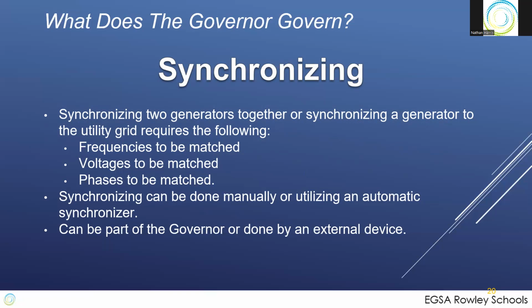When you're looking at, let's say, a generator with a local load and a utility tie point, and now you've isolated from utility, run in island mode for a while, feeding your loads, and now you want to go back on utility, you synchronize back to the utility, and now the genset controller may not be able to see that tie point. You may have another control device at that utility tie point sending a speed trim signal back to the governor on the generator to get it to match utility. At the point of synchronization, you've got to have PTs or voltage detect on both sides of the generator breaker. So synchronizing is another governor function.